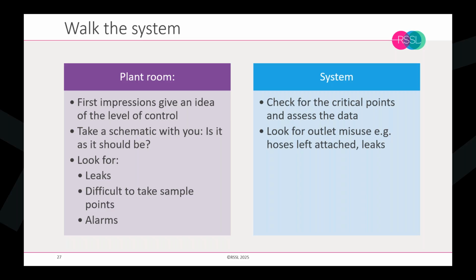So going into a plant room, for example, gives you an immediate feeling for the level of control. It's a good idea to take the facility diagram, a schematic, with you, so you can actually use that to check: is everything exactly where it should be? The diagram has this, but is this in this place? And then look for leaks, because leaks are a problem. One, it gives an idea of the level of engineering maintenance, but particularly leaks in purified and WFI systems. Any leak is a possible bridge for contamination to enter, even if that system is still under pressure. It's not a complete guarantee that you won't get contamination entering the system.